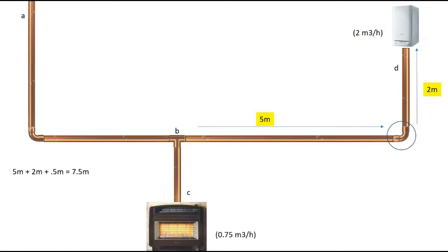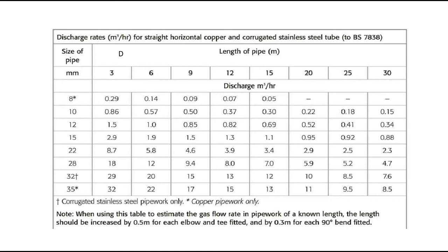Even though it's after the fire, you still carry out the same calculation — there are still two appliances on the system, so you still have to multiply by two. Seven point five times two equals 15 meters of pipe. We're looking for a pipe which will carry two meters cubed per hour through 15 meters, so we go to our chart. We've got 15 meters and we go down until we hit two meters cubed per hour — it's not there, so we take the nearest value above two meters cubed, which in this case is 3.4 meters cubed per hour.